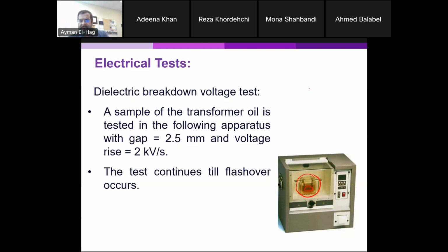So this is something like this, two hemispheres, and the distance between them, as mentioned to you here, is 2.5 millimeter. Now, this is the start button of this test. You start the test. The voltage rise is 2 kV per second. So the test continues until a flashover happens.